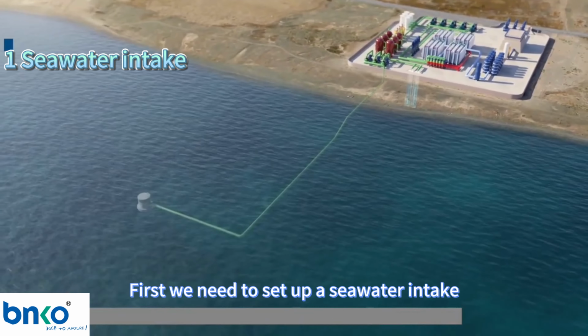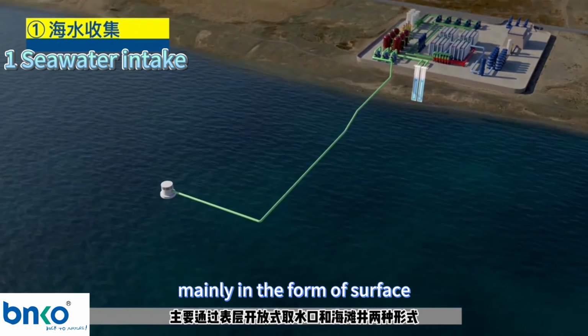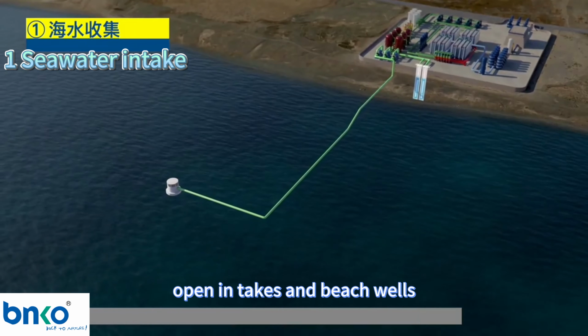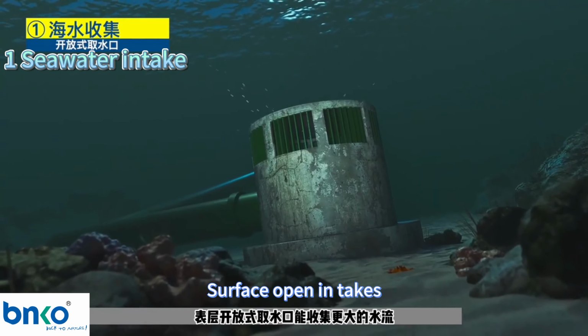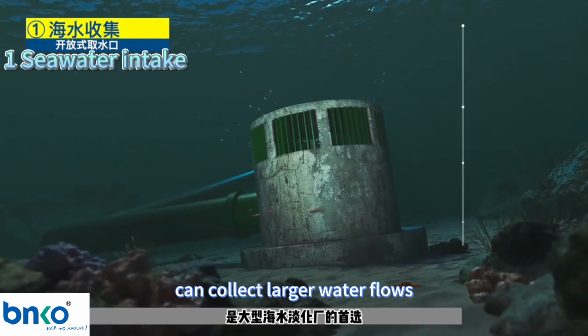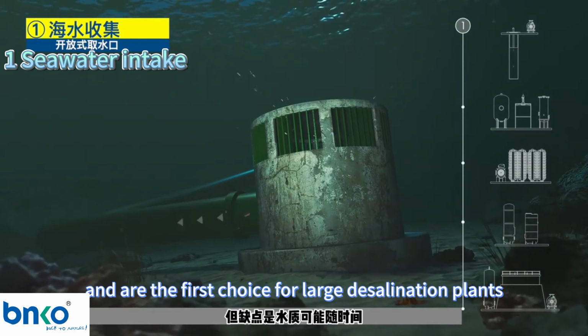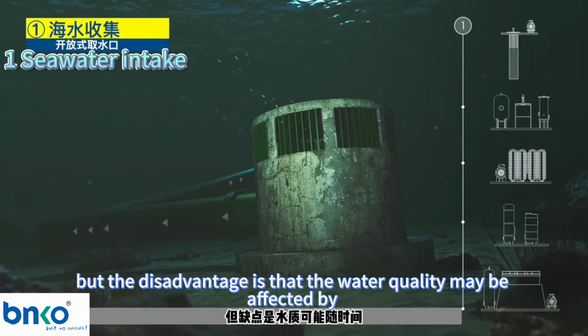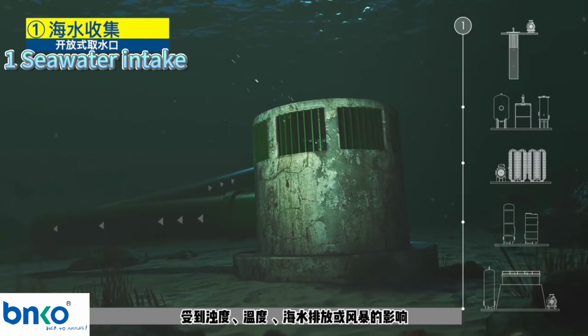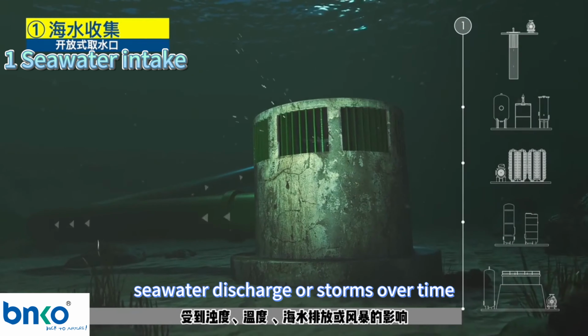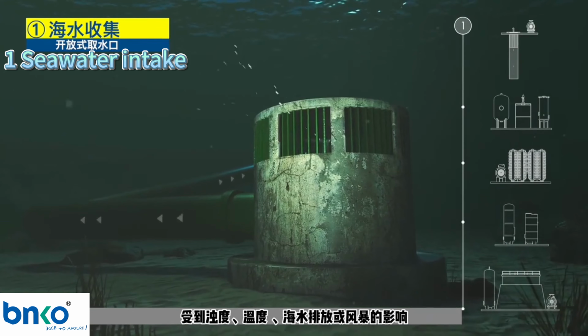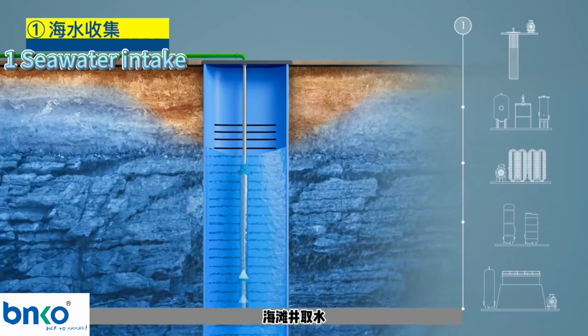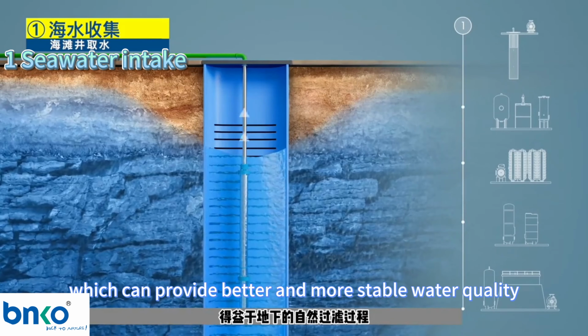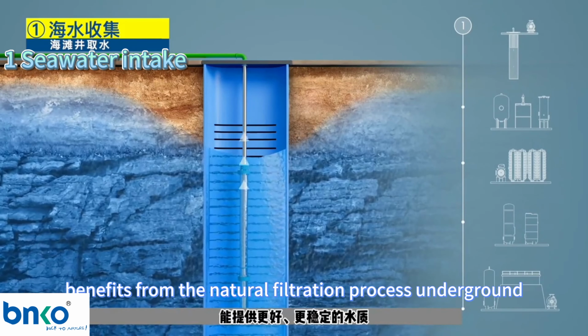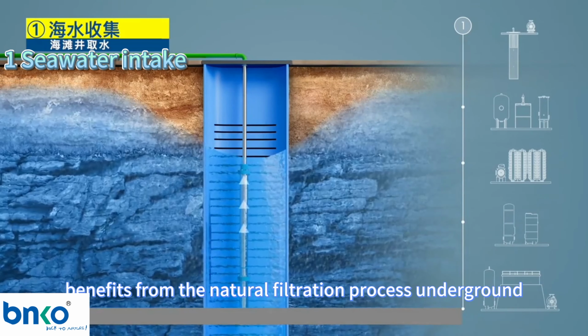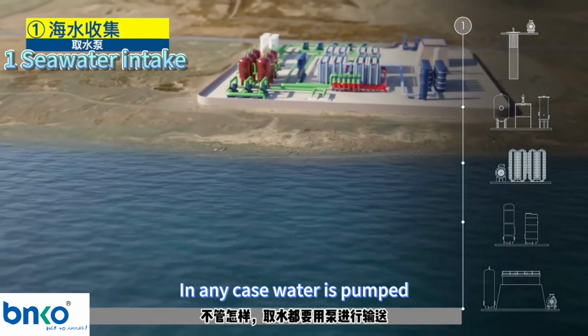First, we need to set up a seawater intake, mainly in the form of surface open intakes and beach wells. Surface open intakes can collect larger water flows and are the first choice for large desalination plants. But the disadvantage is that the water quality may be affected by turbidity, temperature, seawater discharge, or storms over time. Beach wells can provide better and more stable water quality, benefiting from the natural filtration process underground. In any case, water is pumped.